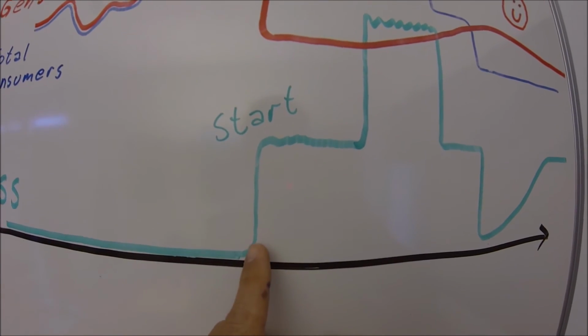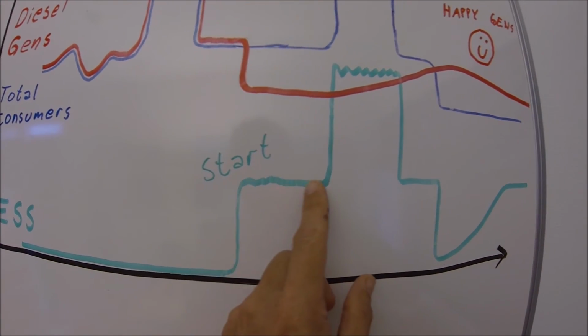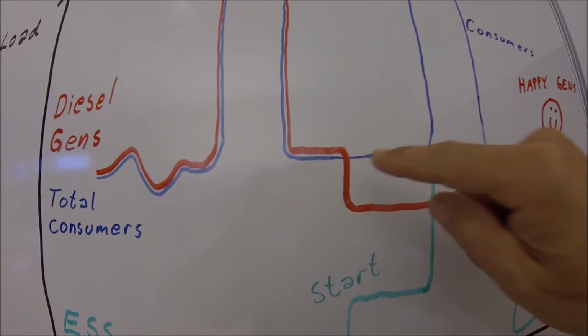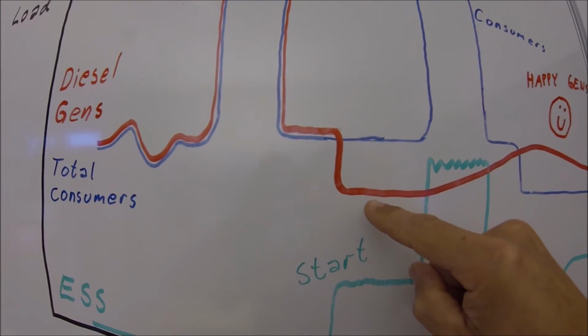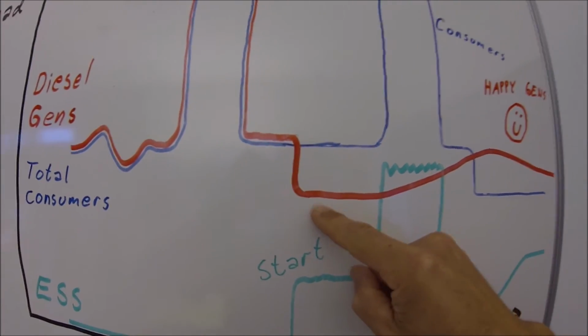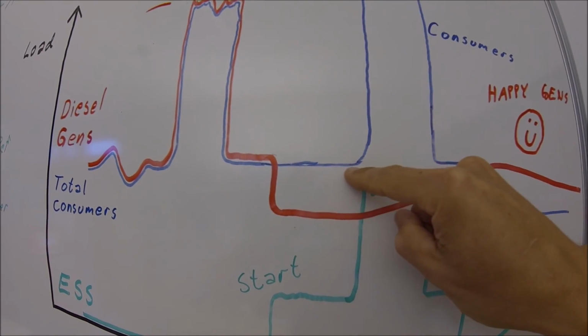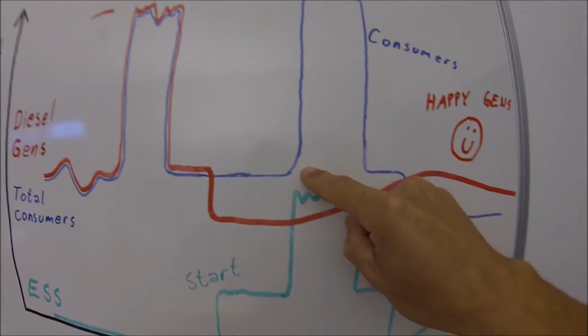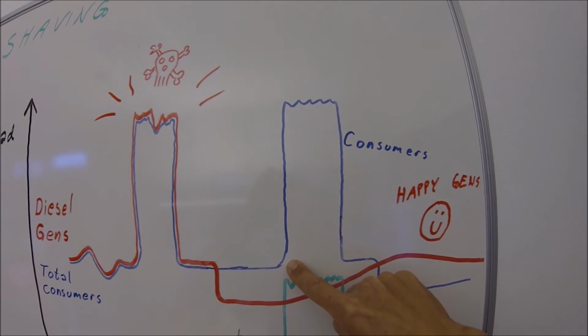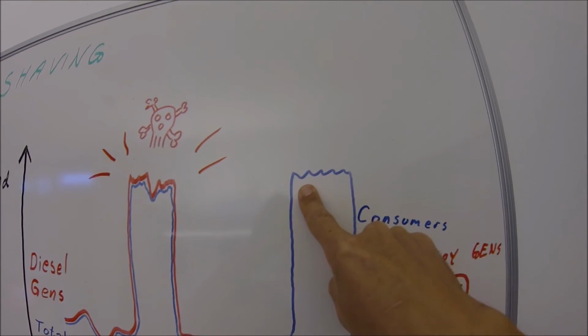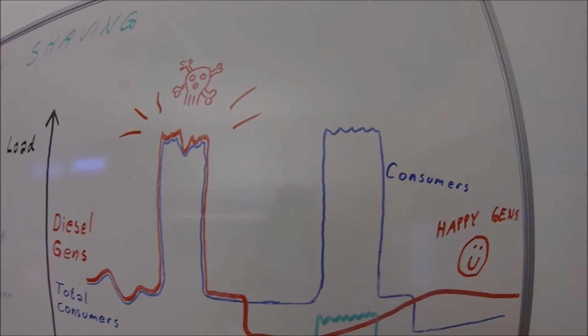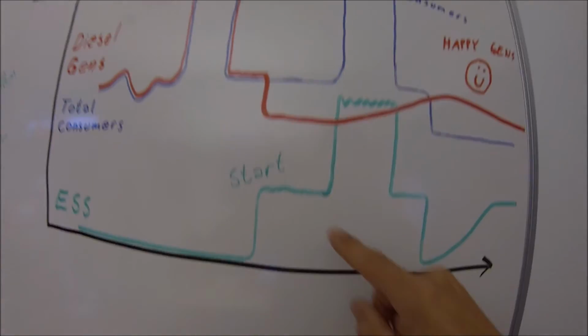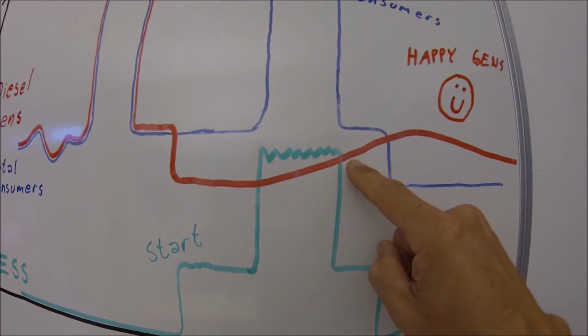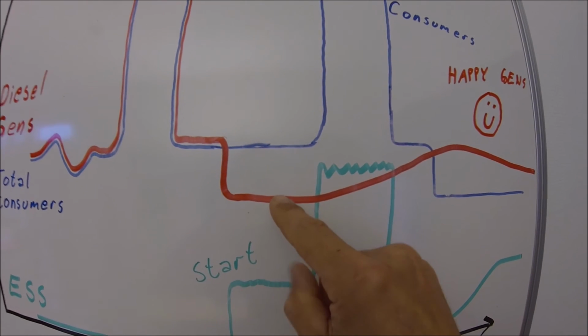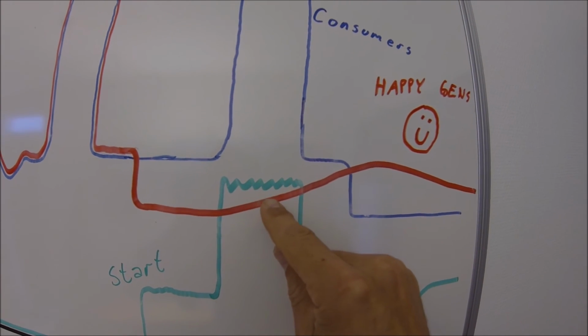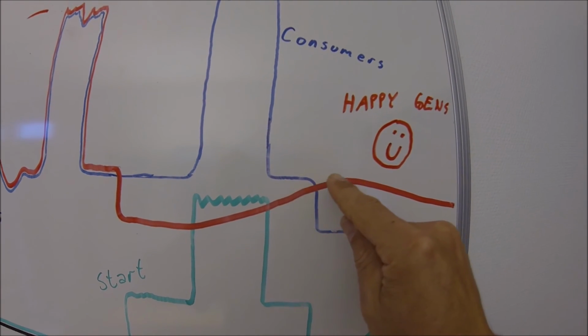Here we start the energy storage. It takes some load immediately, and we can see that the diesel generators are unloaded a little bit. The consumers sit here constantly, and suddenly somebody starts a bow thruster or some big consumer, boom. There is 1 megawatt in 1 second. The battery will provide this power, and the diesel generator only will see a slow increase in power.